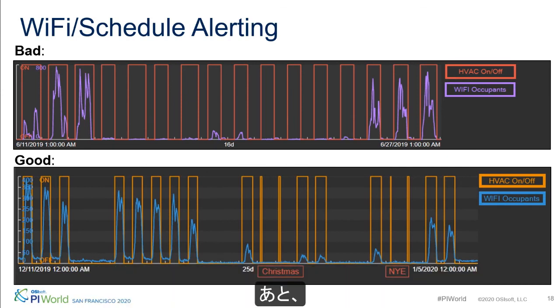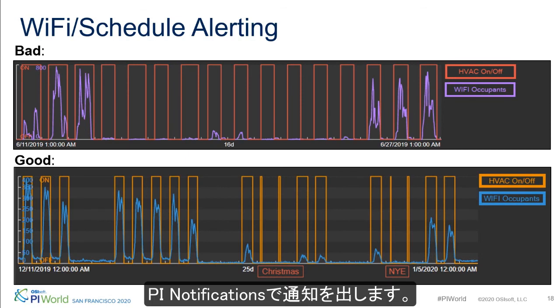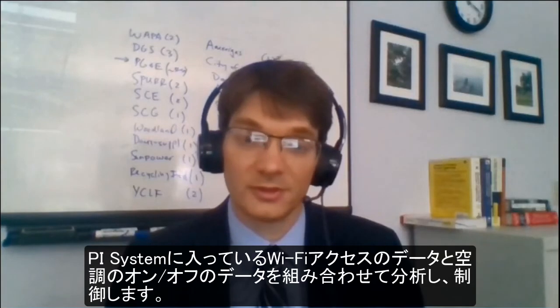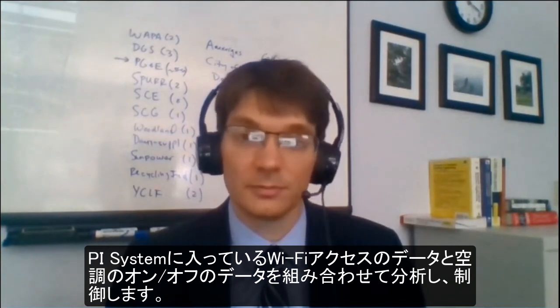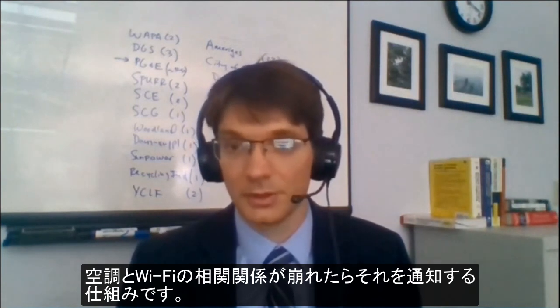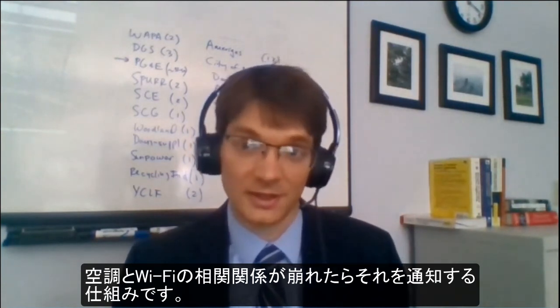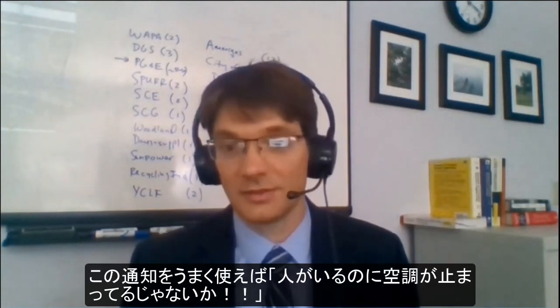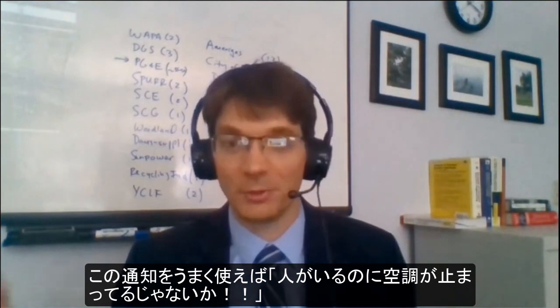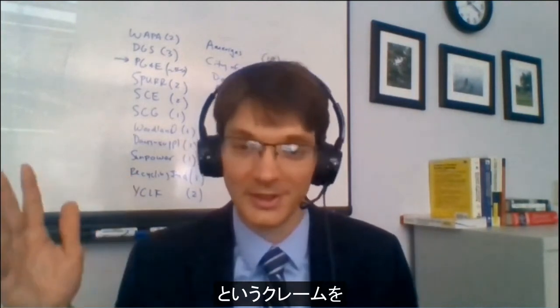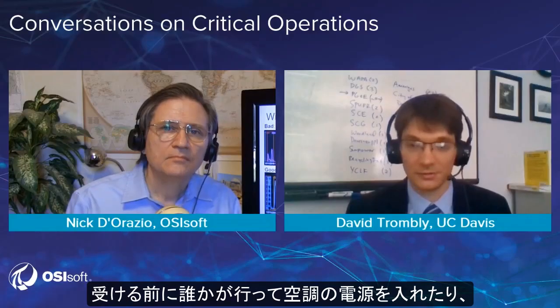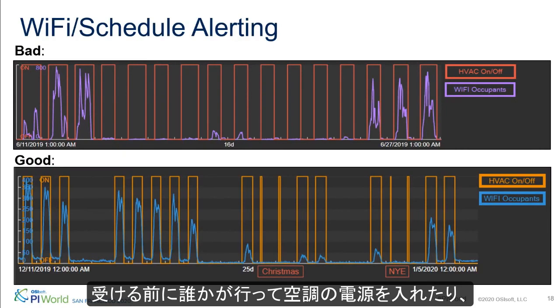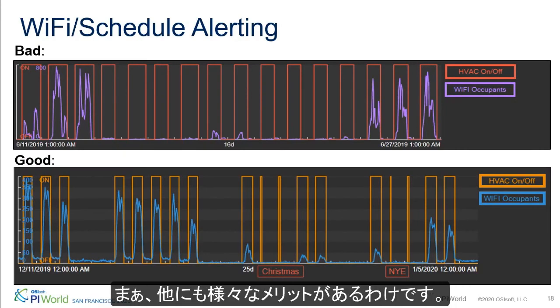And then another thing we've done is we've used Pi notifications, so that if there's times where the Wi-Fi occupancy goes up and the HVAC is off, because it's now all in Pi, this is a use case where the value is the HVAC data combined with the Wi-Fi data. If the HVAC is off and the Wi-Fi occupancy is up, then there's a notification and someone can go in and turn things on, maybe before complaints happen and that sort of stuff.